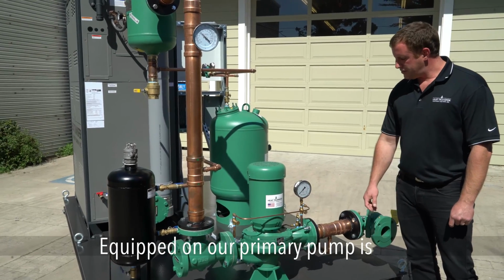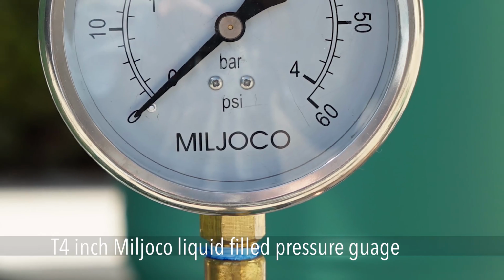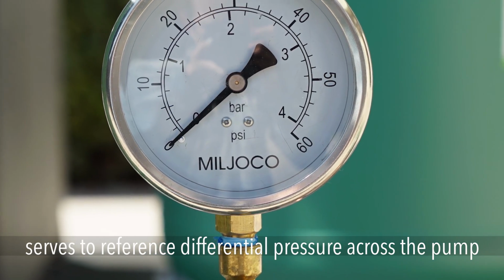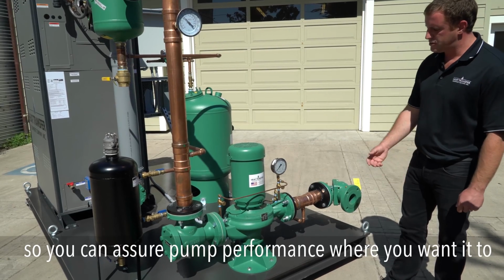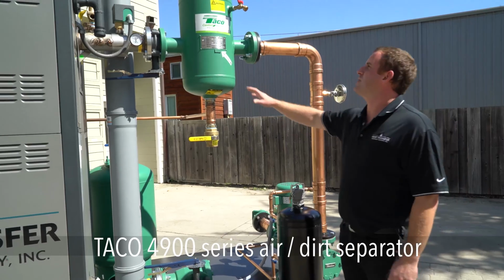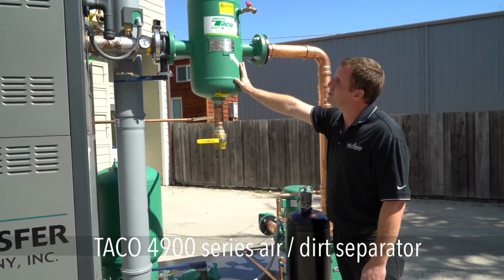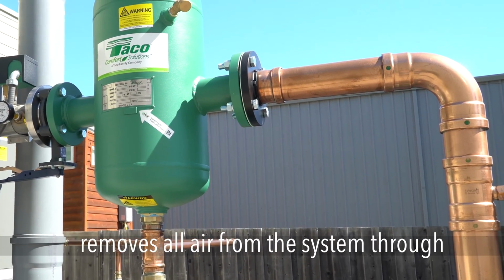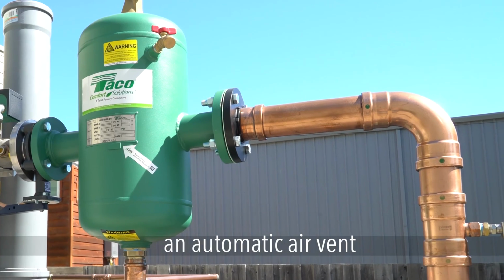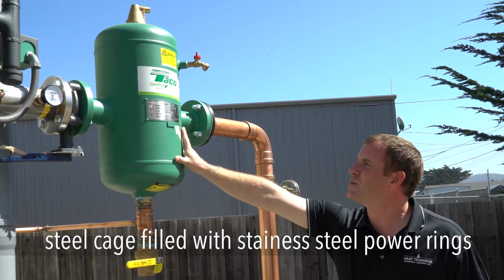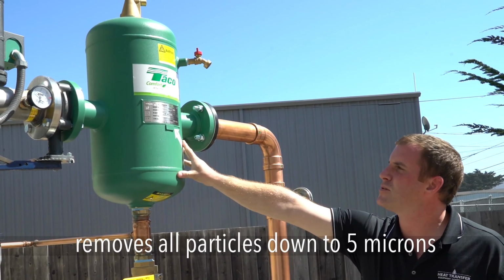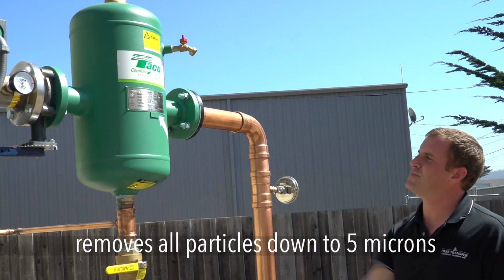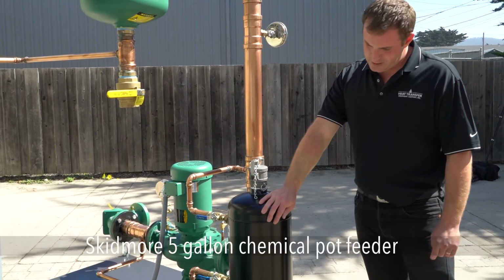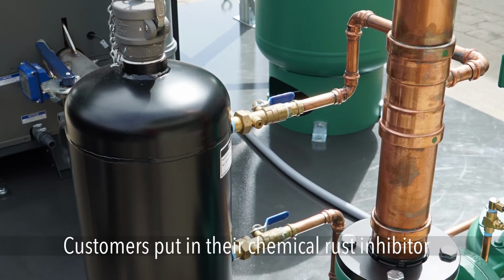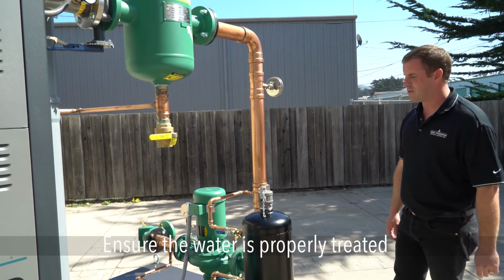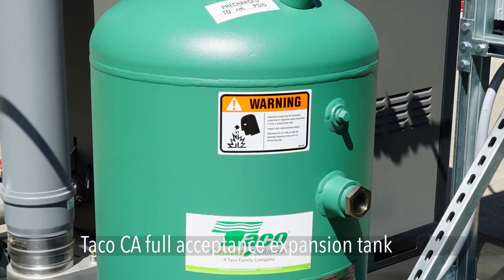Equipped on our variable speed primary pump is a Miljoco 4-inch liquid filled pressure gauge. Serves to reference differential pressure across the pump so that you can assure the pump is performing where you want it to. Our Taco 4900 series air dirt separator. Not only does it remove all air from the system through an automatic air vent located at the top, it's got a steel cage filled with stainless steel pall rings within it. Also serves to remove all particles down to 5 microns. A Skidmore 5-gallon chemical pot feeder. Customers can put in their rust inhibitor, make sure that the water is properly treated for the closed loop system that it is. Expansion tank with a replaceable bladder.